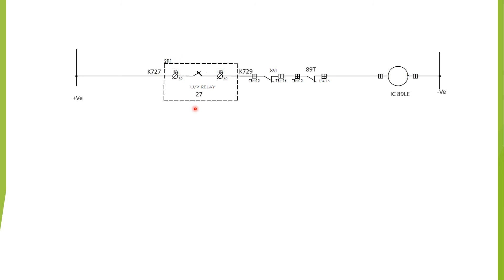The three conditions are: first, the CVT shall have no voltage from either the local end or the remote end — under this condition the under-voltage relay 27 will not operate, the contact remains in NC position, and voltage will pass through. Second, 89L (the line isolator) shall be open. Third, 89T (the bus transfer isolator) shall be open for this feeder. Only then will the interlocking coil be energized and we can operate the line earthing switch electrically.